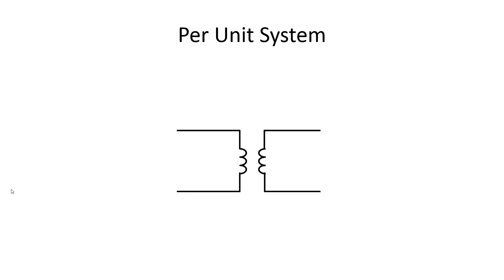Let me apply the full rated voltage to the primary of this transformer: 12 kV. Of course the rated voltage will appear on the secondary, 120 V. But if instead of volts we represent each voltage in percent, we can say we're applying 100% to the primary and getting 100% on the secondary. In per unit, we're applying one per unit and getting one per unit.